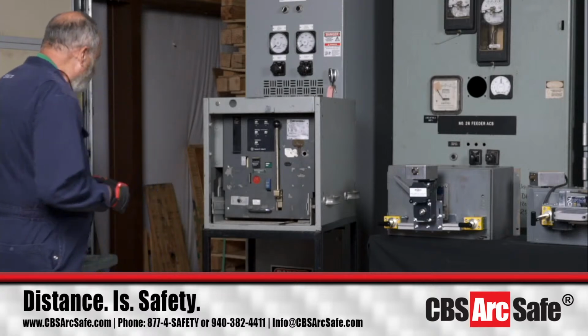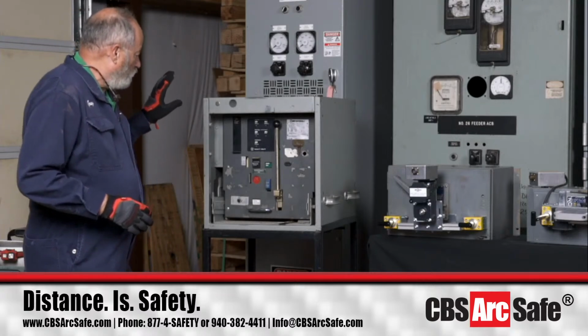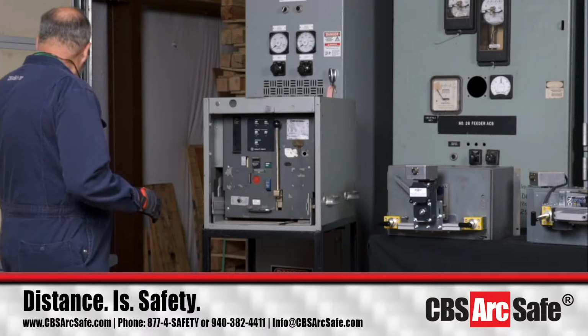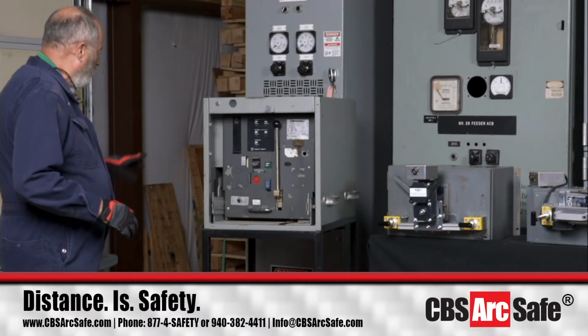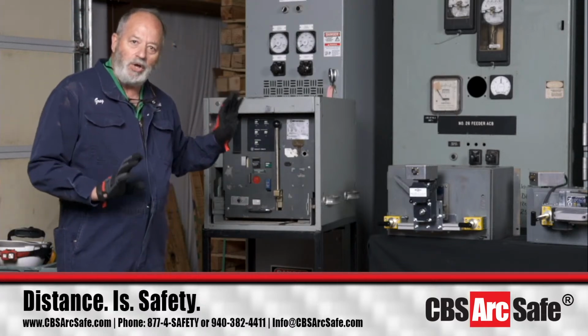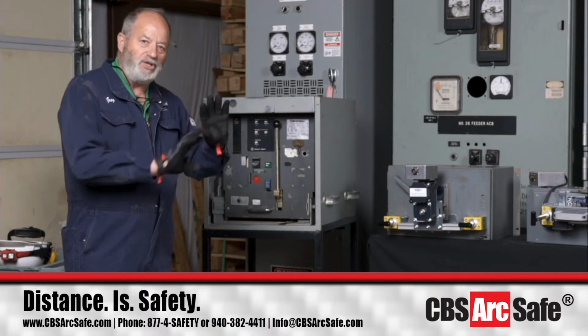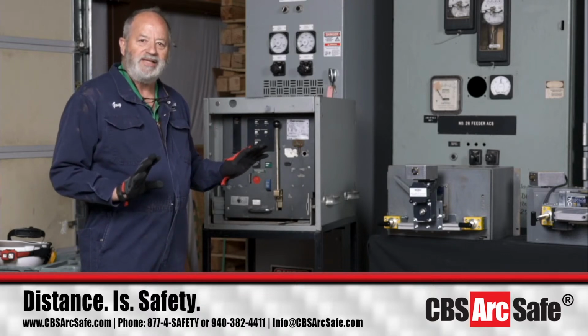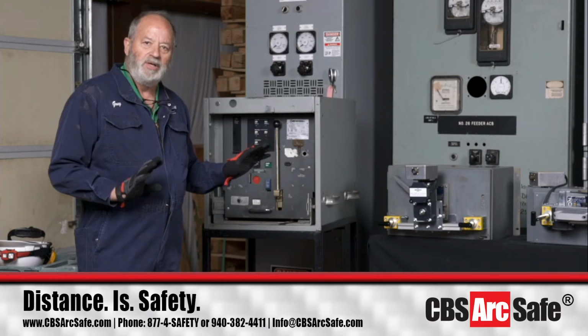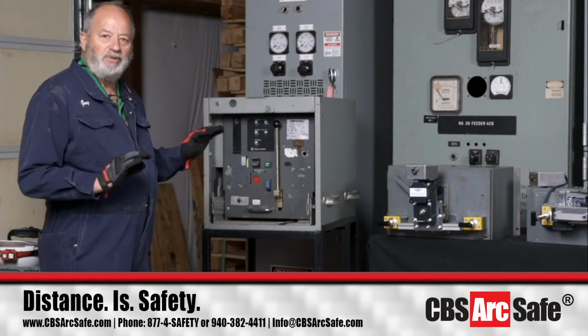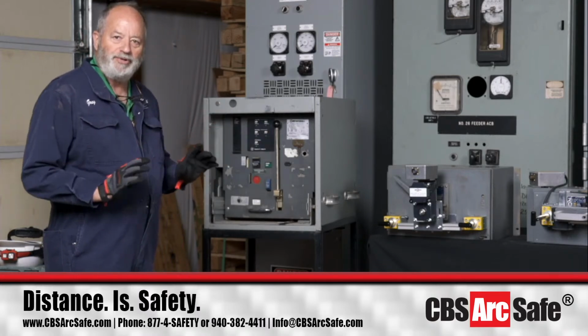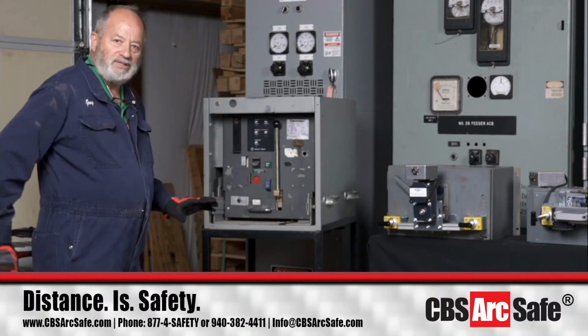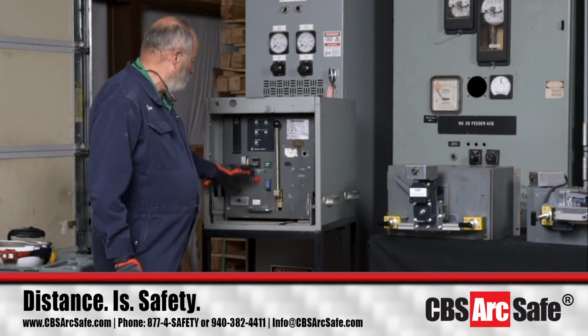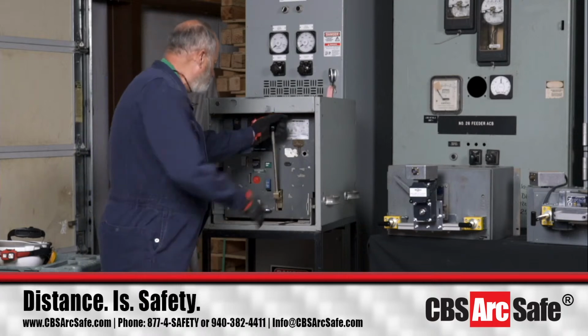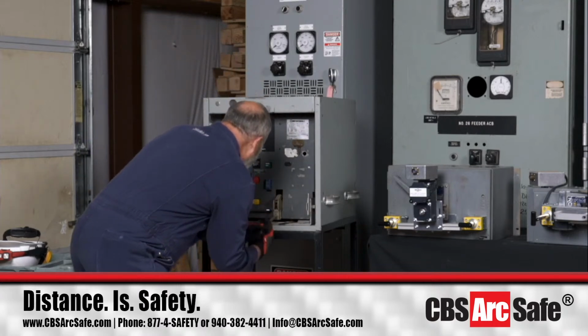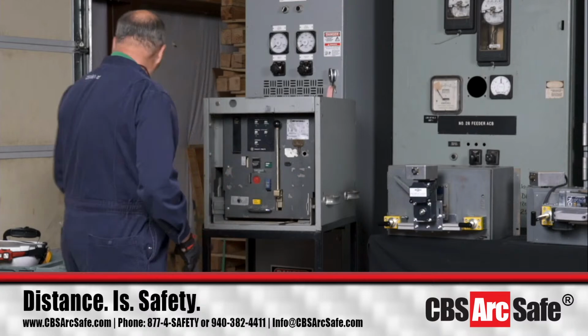Okay, now we're going to show our RSK DS10, and it only closes and trips the breaker. It doesn't matter whether it's an electrically operated DS or a manually operated DS. You would have to charge it with your hand or use the charging motor to do that, and then use the DS10. So before I can put this DS10 on here, I'm going to charge the breaker manually, one stroke down for a manual breaker, okay?